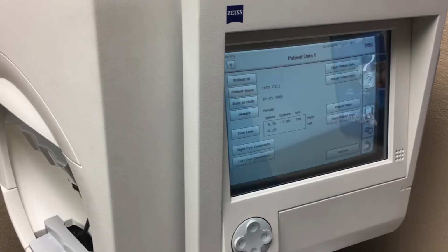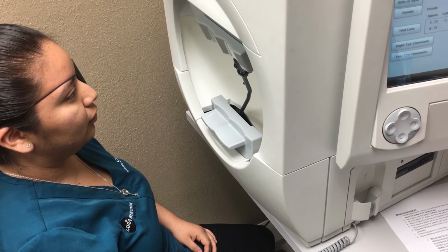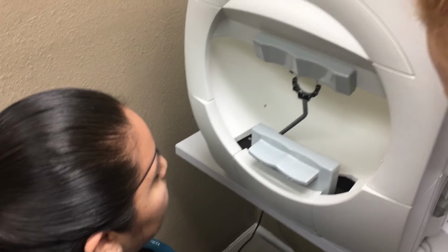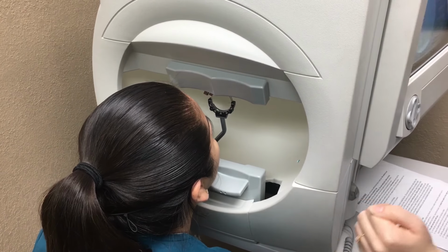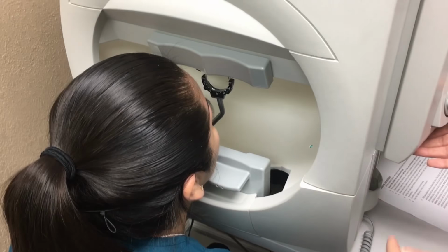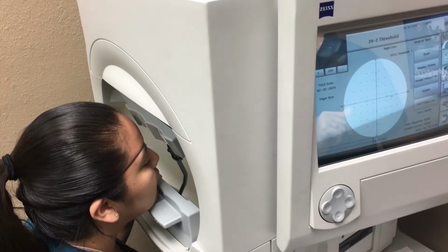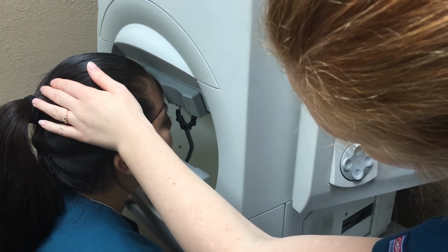I will move the table up or down using this up and down lever because I want the patient to be comfortable. So I'm lowering it to her height. There we go. Okay, CC test. I will have you move forward and you'll put your chin on the left side because we're testing your right eye. All right, let's raise up your chin. I'm using this keypad here to raise up her chin. And then I'm simultaneously lowering the machine so it's comfortable on her neck. We need her chin to be on the rest and her forehead to be all the way up against that bar.